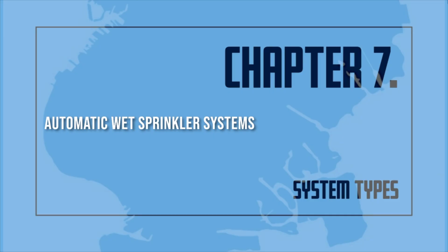Sprinkler systems are required by law in various occupancies. They also may be installed voluntarily by the owner of the building. The sprinklers are installed to protect the building and its residents. The installation of sprinklers has a major effect in reducing fire losses. About 96% of the fires are extinguished or controlled when sprinklers are installed. The 4% failure was due to a variety of causes, including defective piping, closed supply valves, frozen water lines, improper maintenance, and blocked water supply piping.